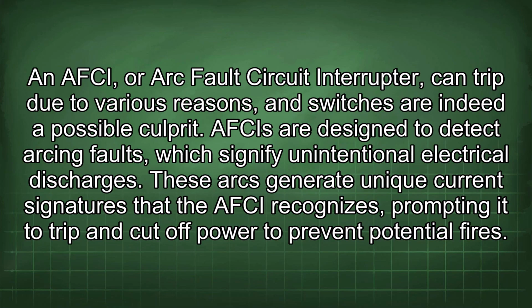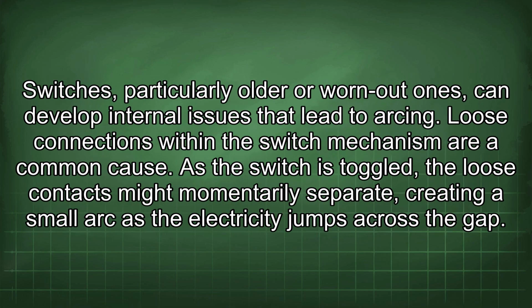An AFCI, or arc fault circuit interrupter, can trip due to various reasons, and switches are indeed a possible culprit. AFCIs are designed to detect arcing faults, which signify unintentional electrical discharges. These arcs generate unique current signatures that the AFCI recognizes, prompting it to trip and cut off power to prevent potential fires. Switches, particularly older or worn-out ones, can develop internal issues that lead to arcing.